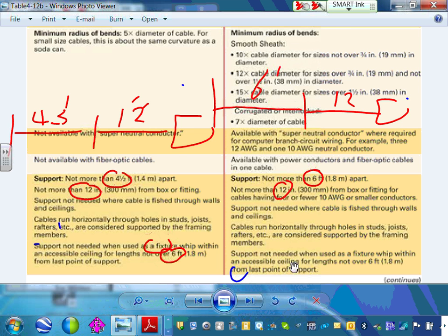Not more than 12 inches for boxes, or number 10 or smaller. Support not needed where cable is fished through; if you fish them, you can also use it. Can you guys see you can use it also as a fixture whip? All these cables, guys, can be used as a fixture whip with 6 feet tied to a fixture. Any comments, guys, about comparing these 2 cables? Comments, questions? Go to the next one, guys.